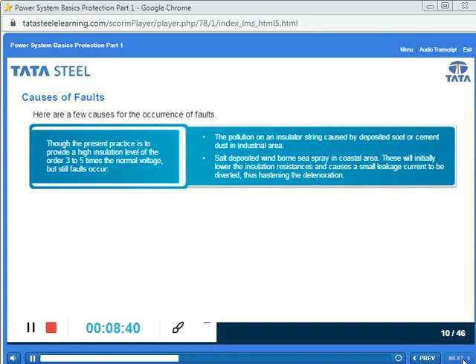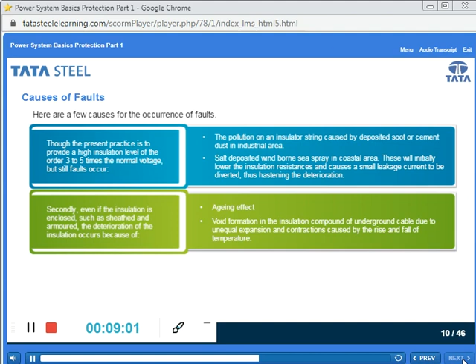Secondly, even if the insulation is enclosed, such as sheathed and armored, the deterioration of the insulation occurs because of aging effect and void formation in the insulation compound of underground cable due to unequal expansion and contractions caused by the rise and fall of temperature.